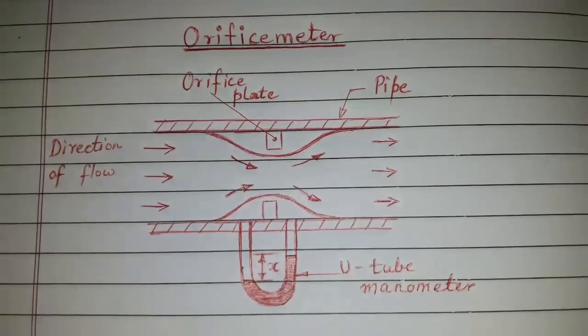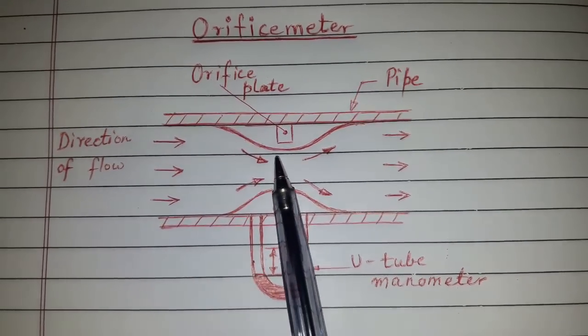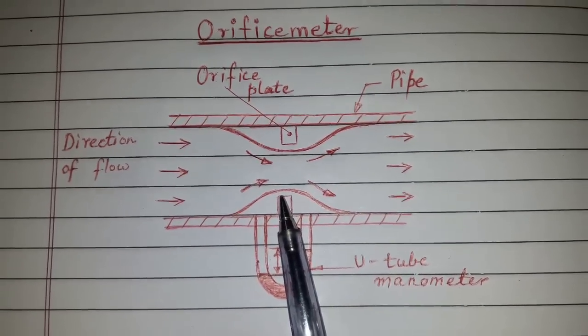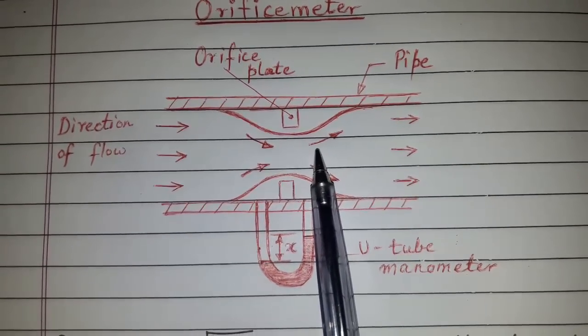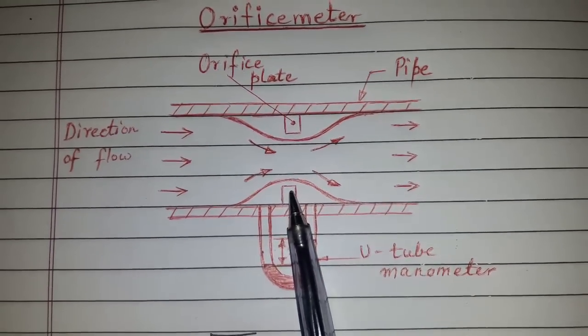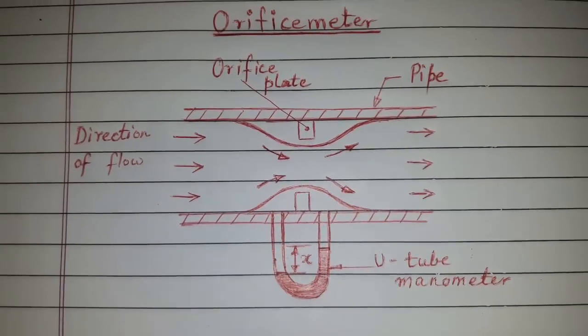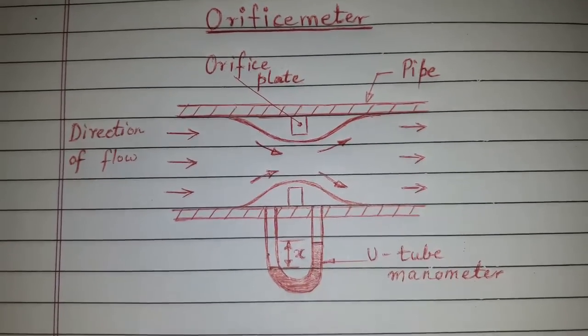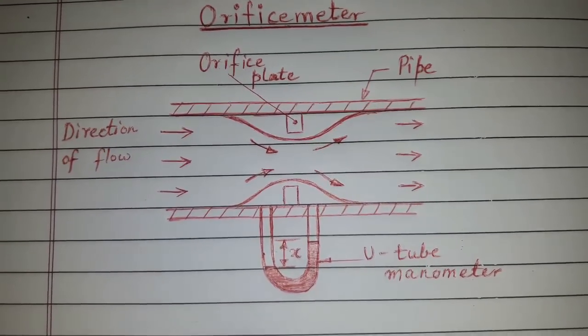Today's topic of discussion is orifice meter. It consists of a flat circular plate which has a sharp edge circular hole called orifice. The plate is fixed concentric to the pipe. The hole diameter can be 0.4 to 0.8 times the diameter of the pipe.